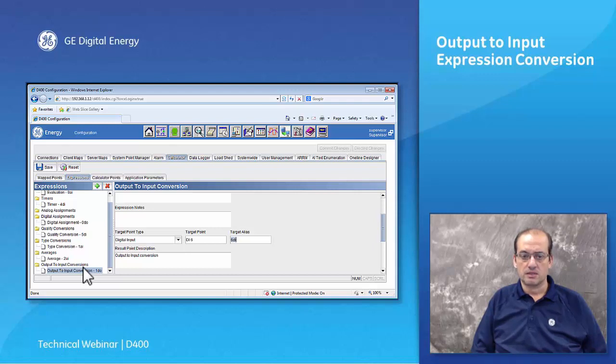The way it's done is we make a digital output available to both masters, and when one master forces that digital output, that's a message that gets converted into a digital input, and that digital input can be retrieved or polled, if you like, by the second master. So master 1 and master 2, we've got master 2 that's going to pick up that value and basically learn whether the first master is in control of the shared resources or is not in control of these shared resources.